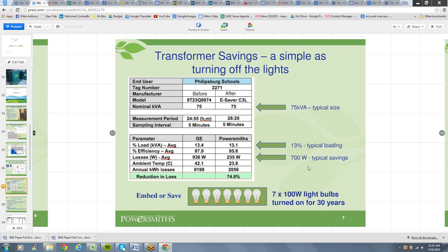This is obviously equivalent to, in reality, seven 100-watt light bulbs left turned on for 30 years. So you're going, whoa, this closet has all those light bulbs that will never burn out. So you start to do the math on that, and even though you may think it's a handful of watts, you start to do that year after year after year, and over increasing energy rates, that's a pretty big number, and this is quantity one transformer. That, by the way, those losses will pay for the transformer roughly 20 times over its life. That's the difference between first cost and life cycle cost for a transformer.